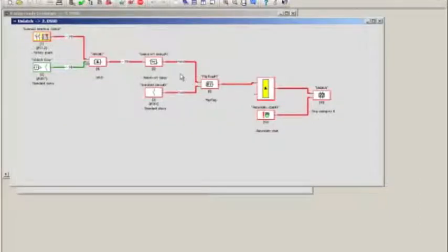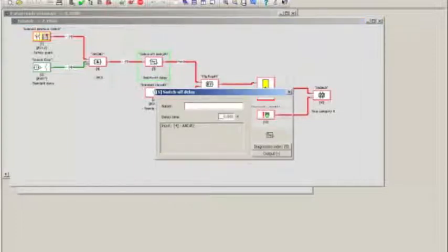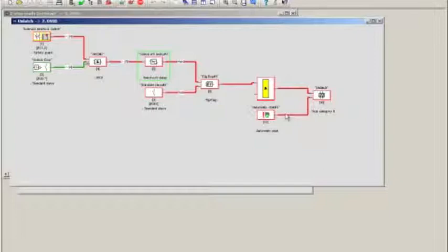The logic that you see here has the property of being self-resetting. That means that after a defined amount of time, and the amount of time is set in this off delay, and I selected 5 seconds here, after 5 seconds the door would either relock, in case the key is inserted, or if I now insert the key, it will immediately restart. So let's do this again.